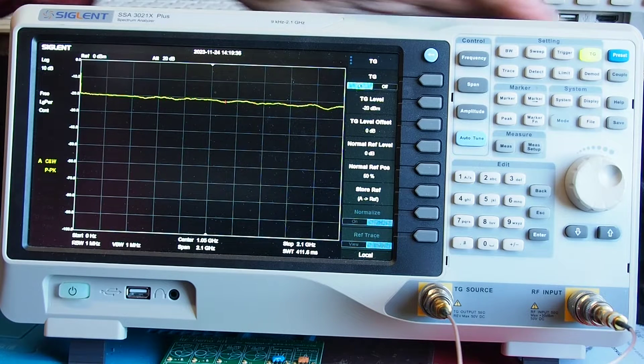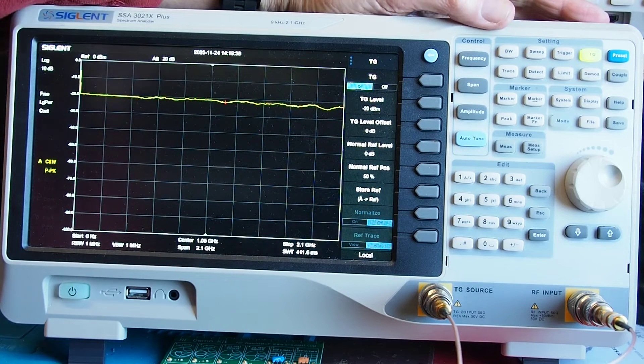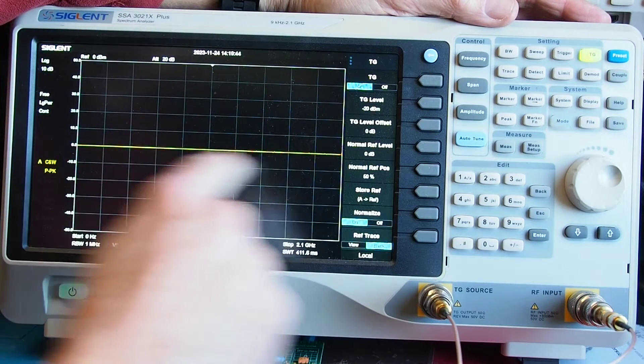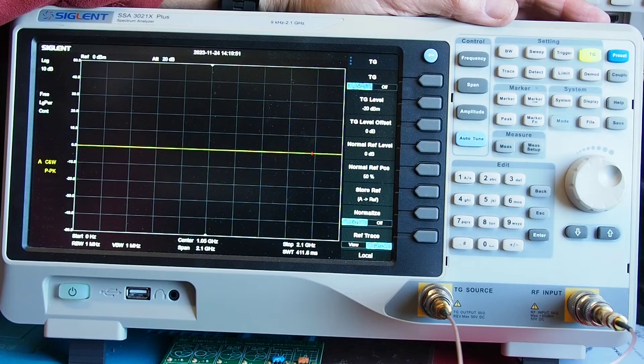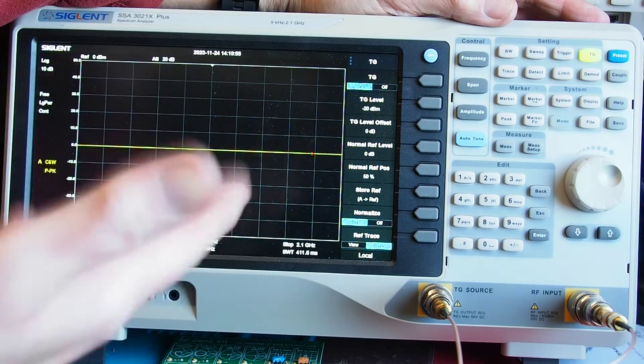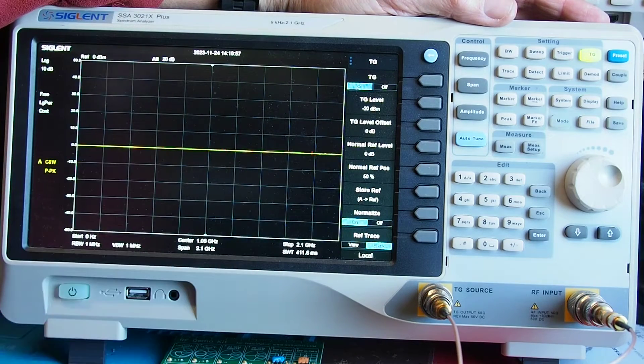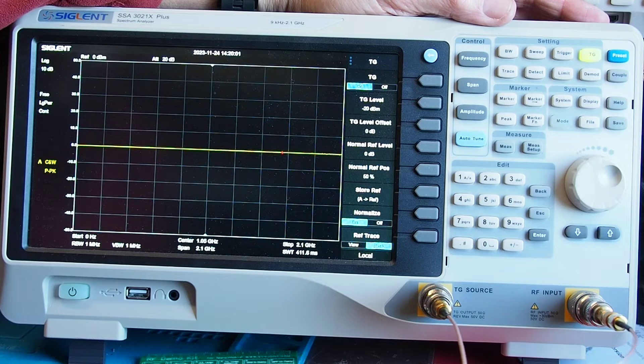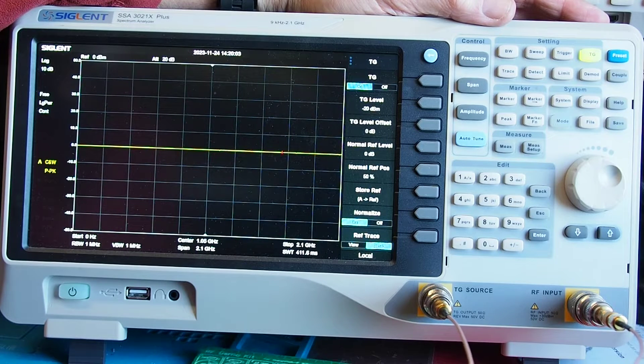Now the analyzer does give you an option to do something about that so if we select store and then select normalize it will draw a straight line but what it's done here is actually it's corrected for any imbalance in output so any measurements we do later will have that correction applied to them.